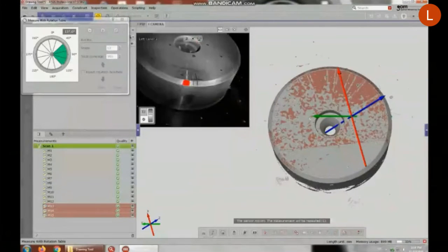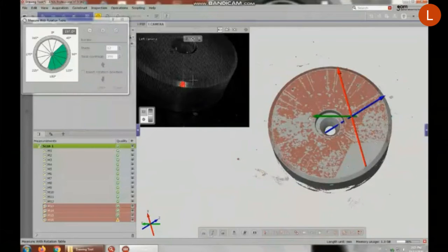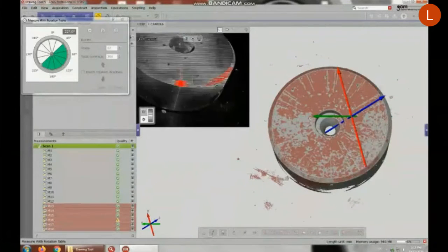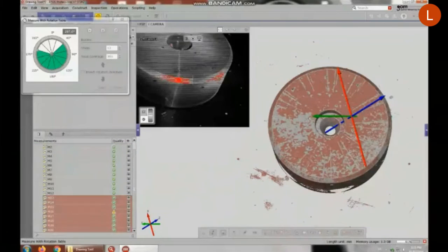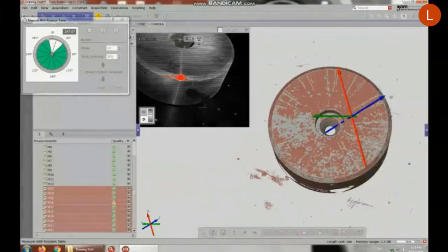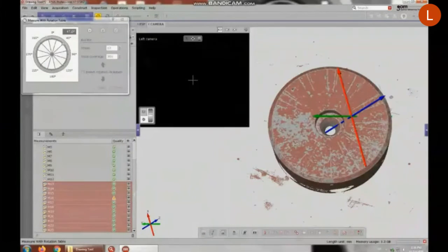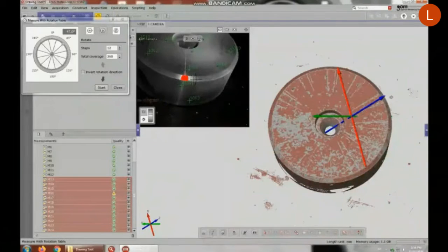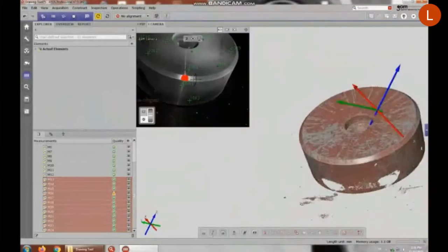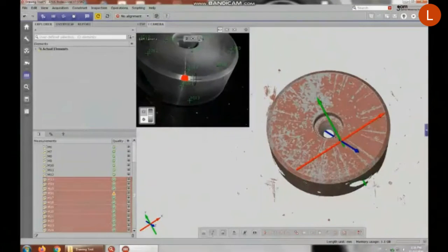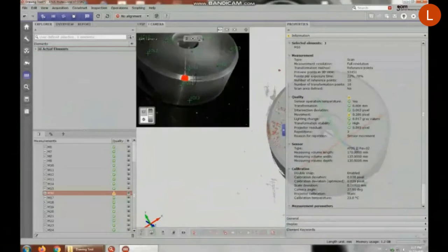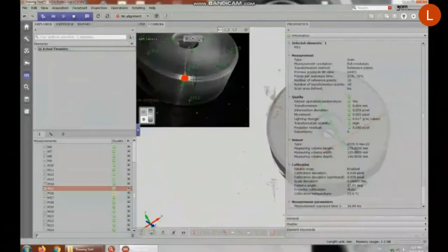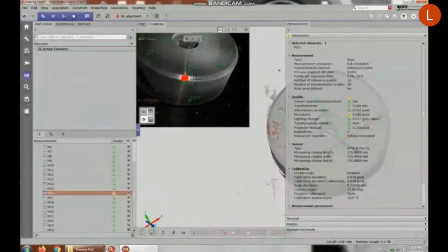To completely digitize the surfaces of the drawing tool, a different relative position between the sensor unit and the scanned objects is set, followed by another 12 measurements. For measurement 16, the software detected a movement with a value of 0.386 pixels, which is above the acceptable limit. The measurement number 16 is deleted.